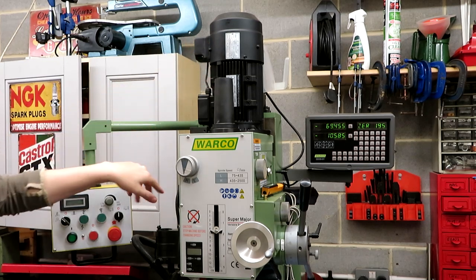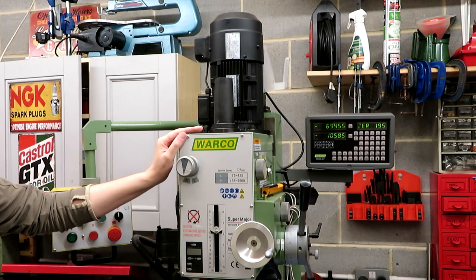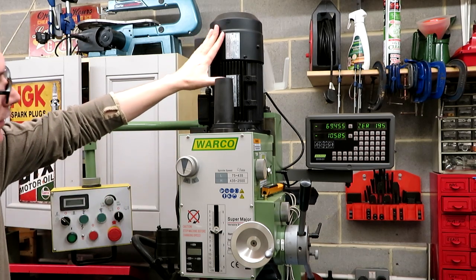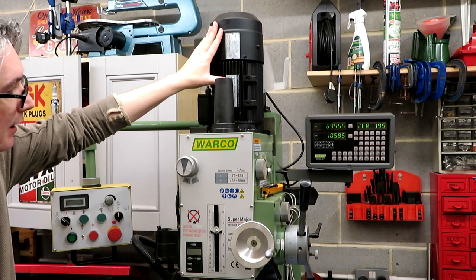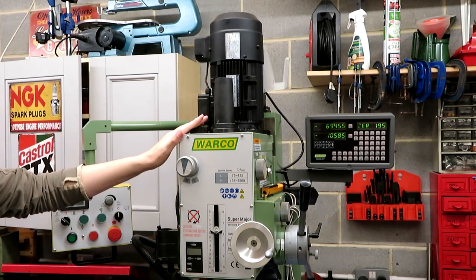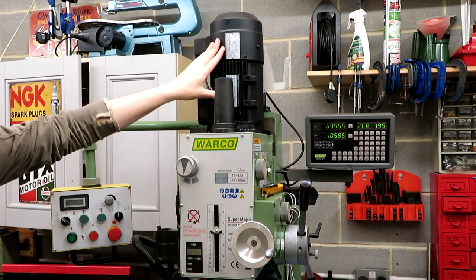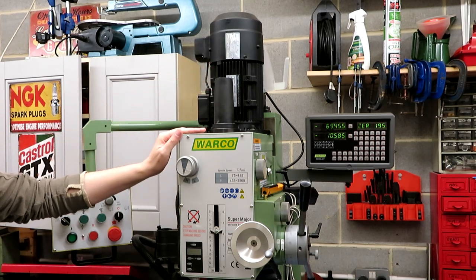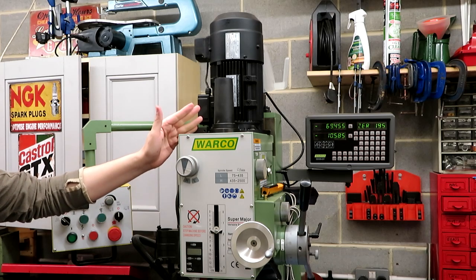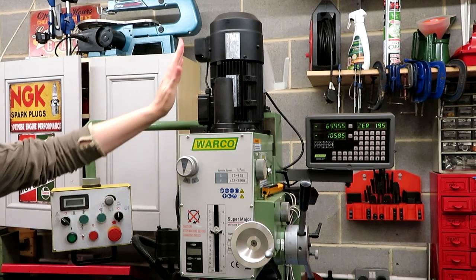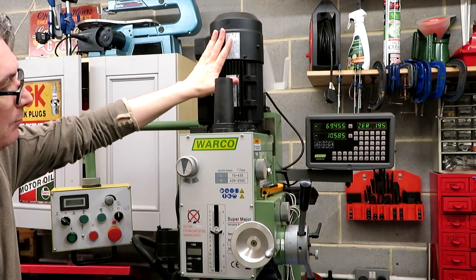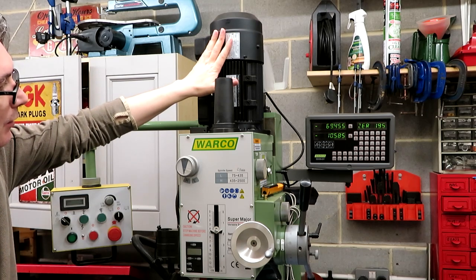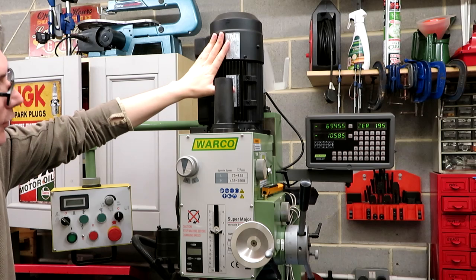So if we were to look in the control panel at the back of the machine, what we'd find is a variable frequency drive, and that takes the single-phase power supply from my house and chops it up and converts it into three-phase, which this motor requires. Apart from doing the conversion between single phase and three-phase, the variable frequency drive, well, the clue is in the name. You can change the frequency of the power going to the motor, and you can control the speed of the motor by changing the frequency of the supply to it.